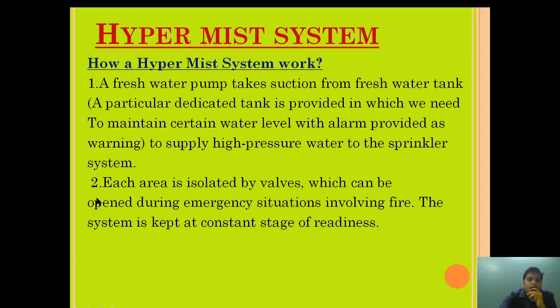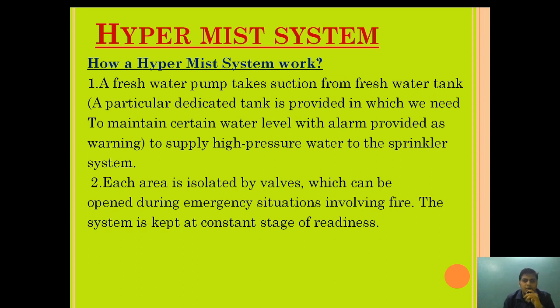Now, how does a Hypermist system work? A fresh water pump takes suction from a dedicated fresh water tank. A particular dedicated tank is provided, and we need to maintain a certain water level with an alarm provided as a warning. On a ship, a specific tank — for example, the starboard tank — is dedicated for the Hypermist system, with a marking indicating the alarm level. If water goes below that level, the alarm activates. Each area is isolated by a valve which can be opened during a fire emergency.